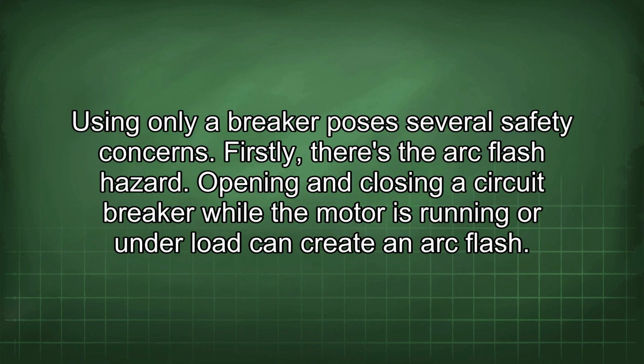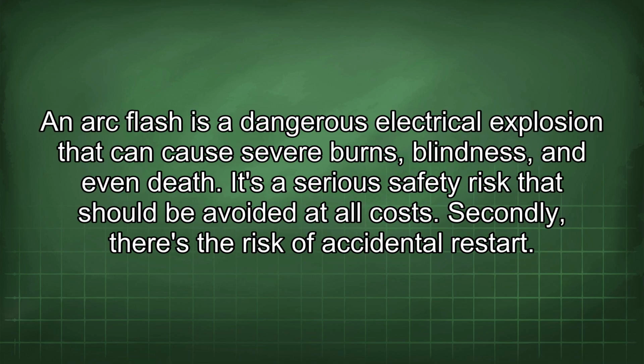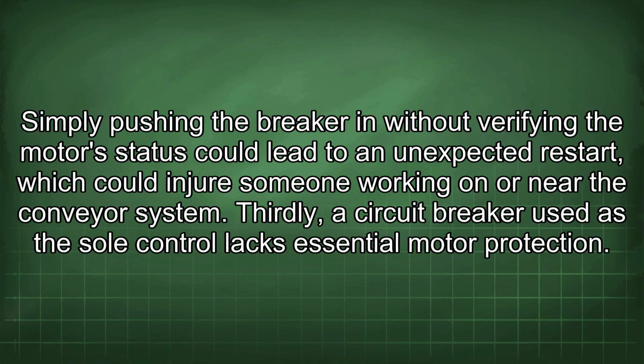Using only a breaker poses several safety concerns. Firstly, there's the arc flash hazard. Opening and closing a circuit breaker while the motor is running or under load can create an arc flash. An arc flash is a dangerous electrical explosion that can cause severe burns, blindness, and even death. It's a serious safety risk that should be avoided at all costs. Secondly, there's the risk of accidental restart. Simply pushing the breaker in without verifying the motor's status could lead to an unexpected restart, which could injure someone working on or near the conveyor system.